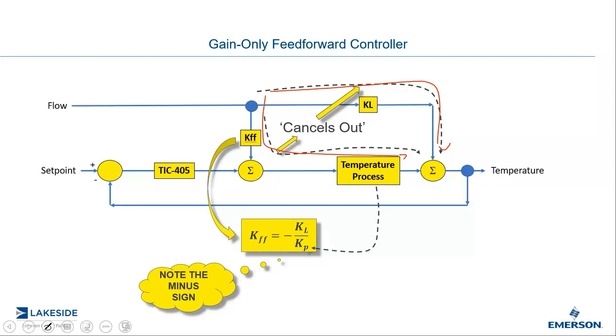So this is the same picture I showed you before. There's my flow controller and my temperature controller, and they're all tuned up. I'm going to make a change to the feed-forward - oh, that's right, I can only change it while in manual mode, because it's in velocity form.